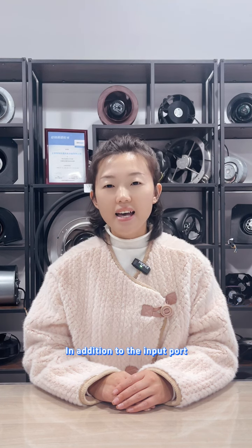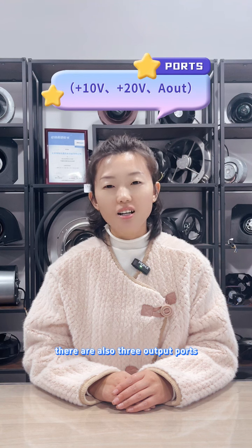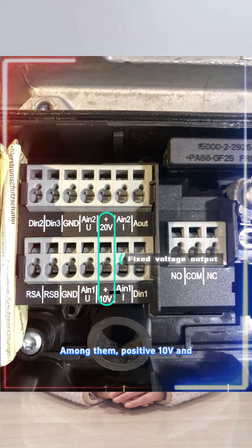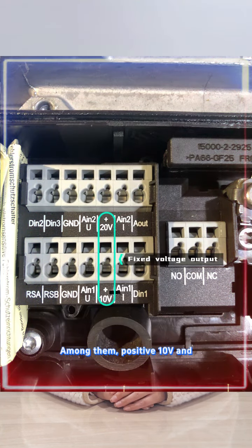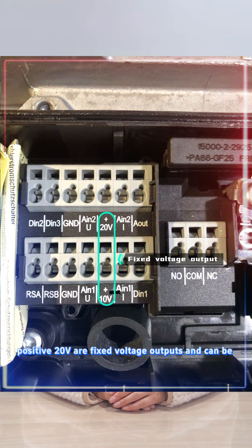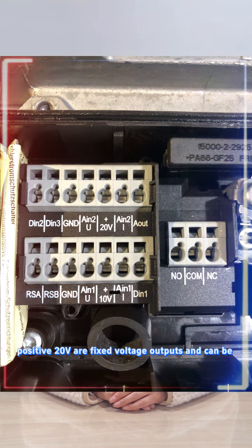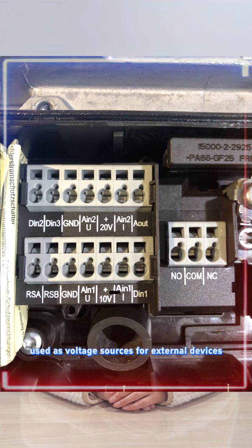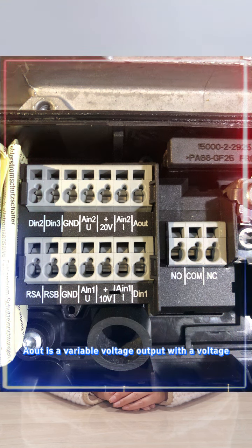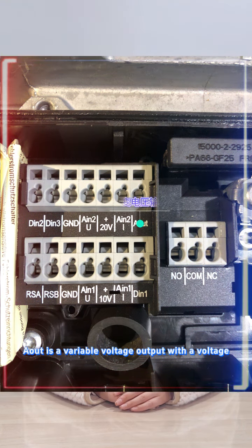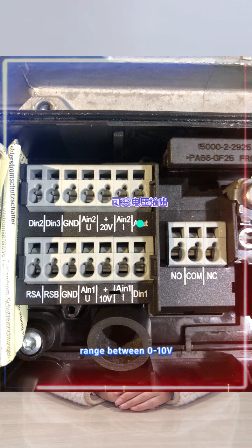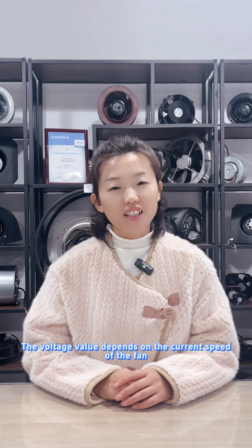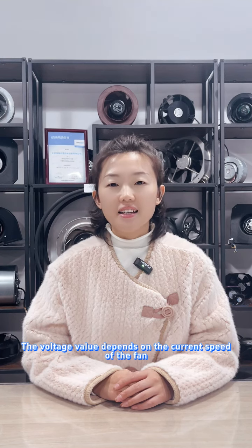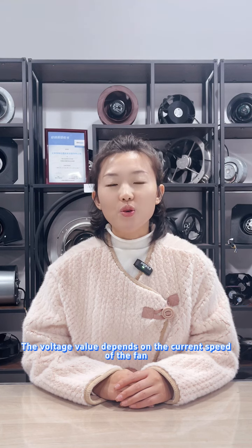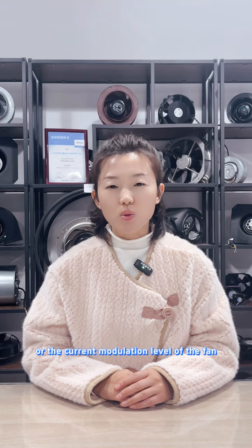In addition to the input port, there are also 3 output ports. Among them, positive 10 volt and positive 20 volt are fixed voltage outputs and can be used as voltage sources for external devices. Aout is a variable voltage output with a voltage range between 0-10 volt. The voltage value depends on the current speed of the fan or the current modulation level of the fan.